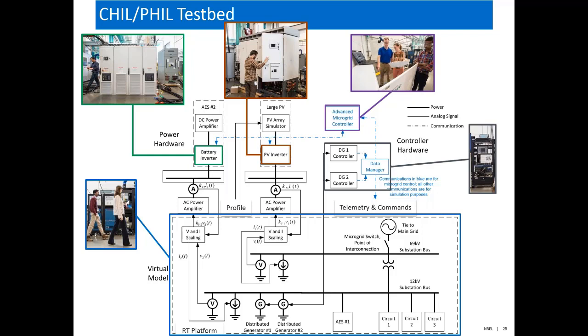In the top center you can see the large-scale PV setup. We used a MagnaPower to represent the PV DC side, feeding into an SMA Sunny Central 500 kilowatt commercial PV inverter, the exact same make, model, and firmware used in Borrego Springs. Of course they have 26 megawatts, and we only had one unit of half a megawatt, so with a scaling factor of 52-fold between the real world and the virtual world, I effectively had a 26 megawatt solar farm sitting in my lab for this testing.